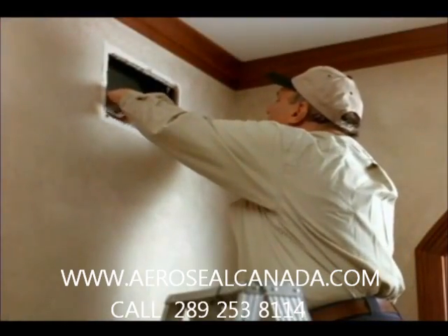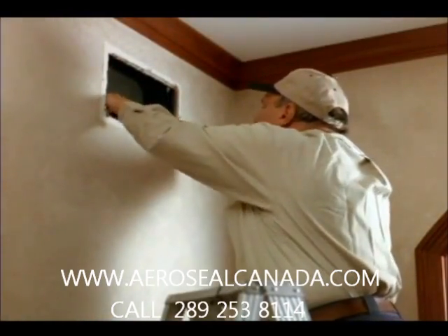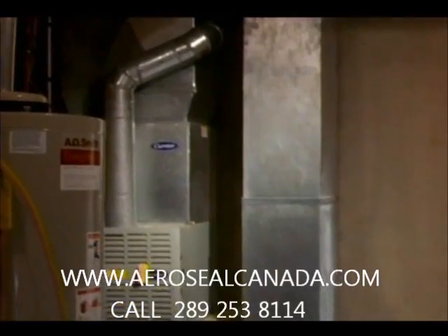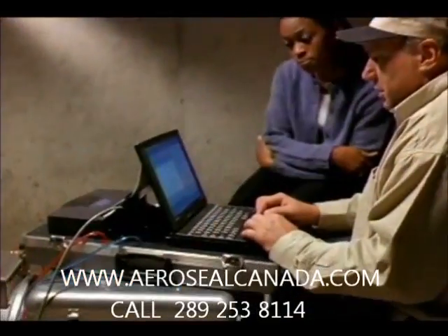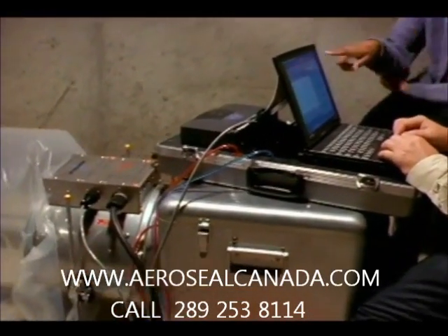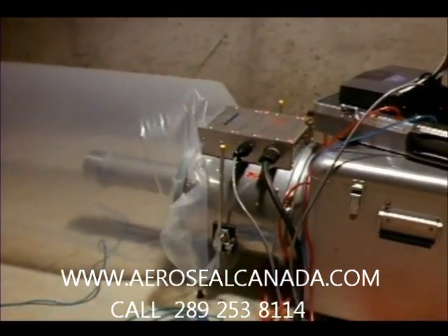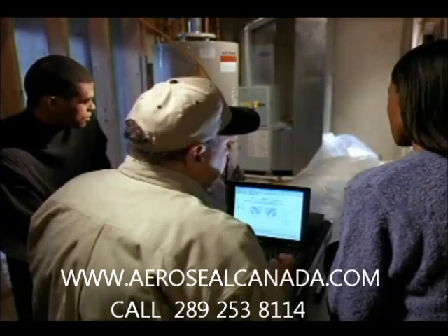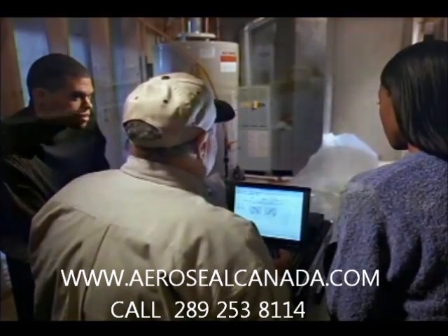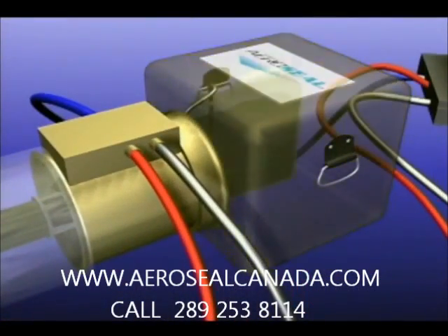The technician will install foam plugs into all air duct openings. An access hole is cut into the supply or return plenum, and a temporary collar is attached. The Aeroseal injection machine is then connected to the duct system using a long, flexible plastic tube. A patented computer-controlled injection machine heats up adhesive particles suspended in a liquid.